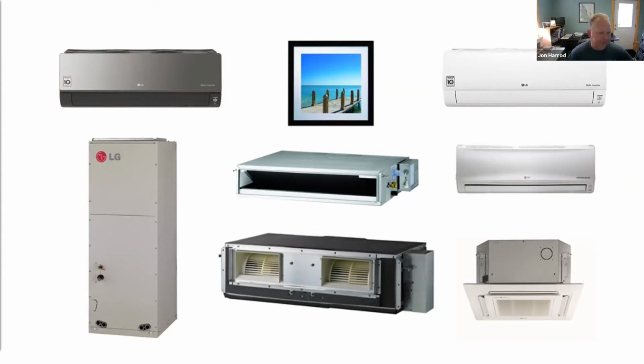And one of the things that I find most exciting, and I think is going to really help this scale, is that these cold climate heat pumps now have full-sized air handlers that are, in many cases, suitable to be swapped out directly for a forced air, natural gas, or oil or propane furnace. And so this way we can provide central heating and cooling, fully ducted. Usually there's some calculation and some duct modification that needs to take place to get those to work well.